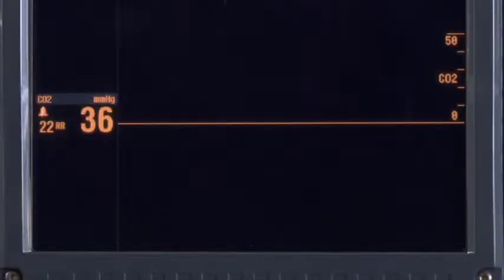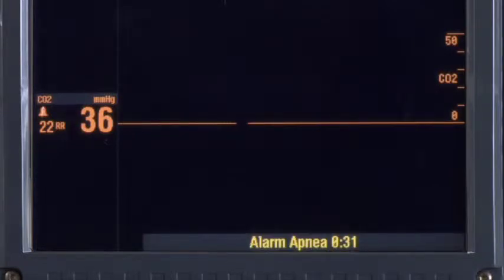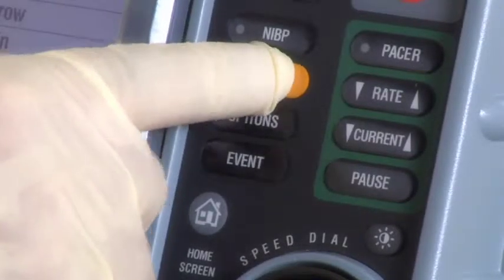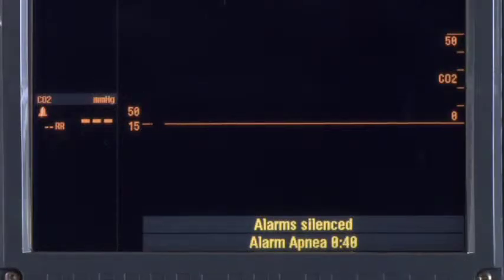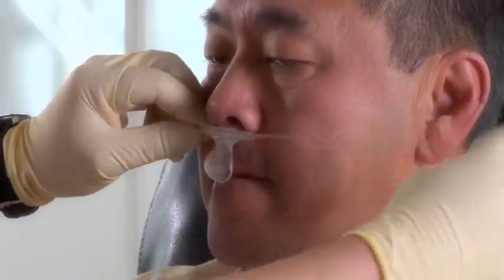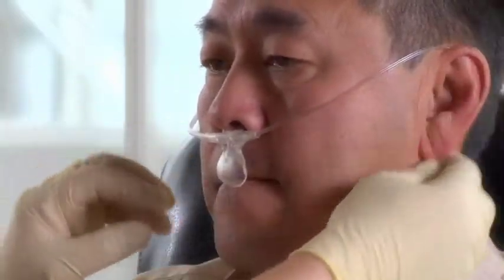The end-tidal CO2 monitor has a built-in apnea alarm. Once a valid breath has been detected, the apnea alarm triggers if the monitor hasn't detected a breath for 30 seconds. The message, "Alarm Apnea," appears, and the time since the last detected breath. You can temporarily silence the alarm tone by pressing Alarms. First, check the patient and whether the filter line is still attached. The alarm clears when the next breath is detected.